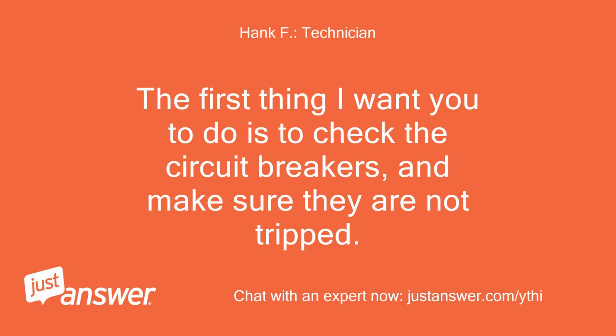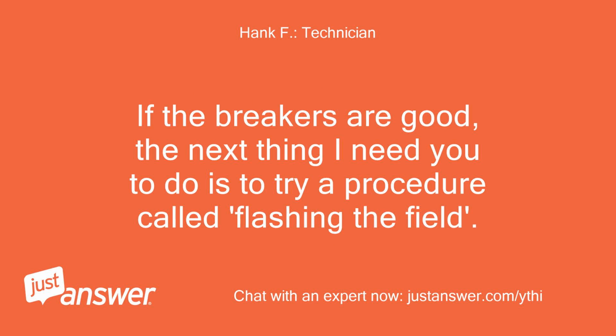The first thing I want you to do is check the circuit breakers and make sure they are not tripped. If the breakers are good, the next thing I need you to do is try a procedure called flashing the field. Here is how to do it.